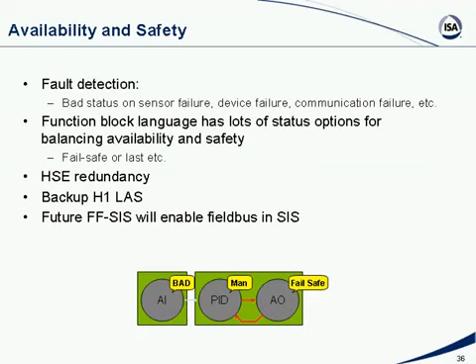Field bus has plenty of diagnostics and fault detection. So if there's a sensor failure, a device failure, or a communication failure, you get a bad status. This gets propagated through the function block — from the transmitter, it puts the PID in manual, and that brings the valve positioner to a fail-safe state. All these interlocks are built into the function blocks; I don't need to configure them, it's already there for you to use. Very easy — this is really one of my favorite features of field bus.